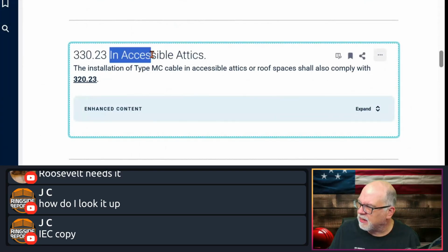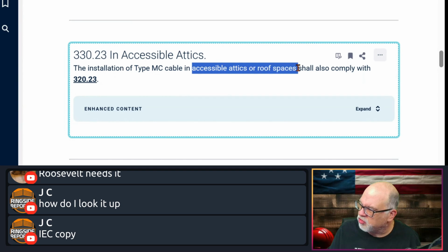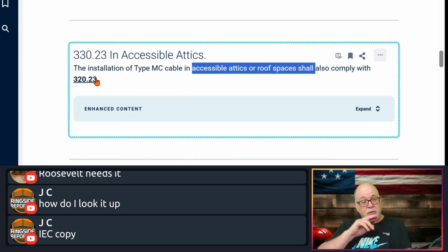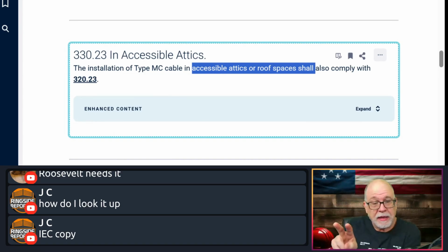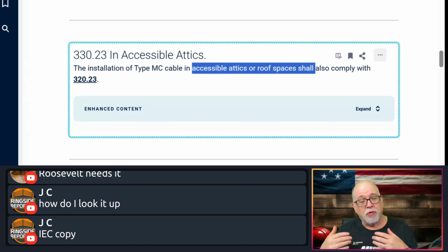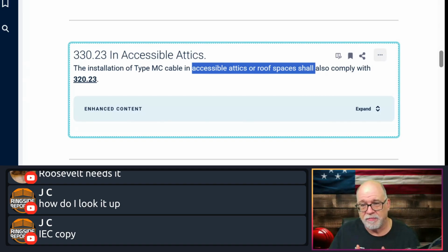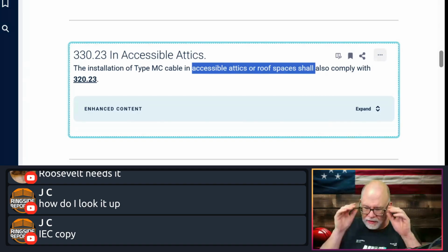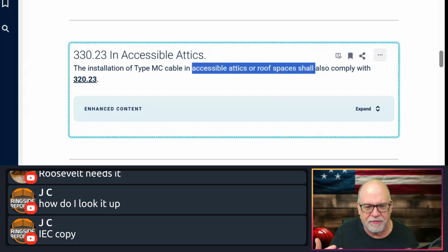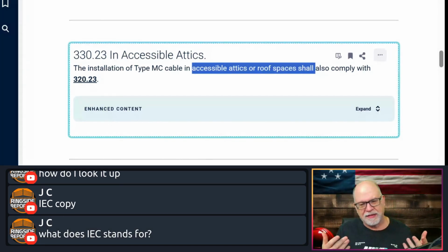Next, in attic spaces, the installation of type MC cable in accessible attics or roof spaces shall comply with 320.23. Now, you all know that 320 is AC cable. And it does the same thing for non-metallic sheath cable, right? It references 320.23. The reason it does that is, and we don't do this a lot in the code, it saves regurgitating information because the rules are going to be exactly the same.